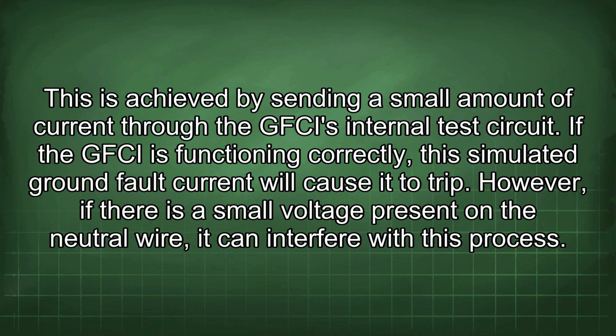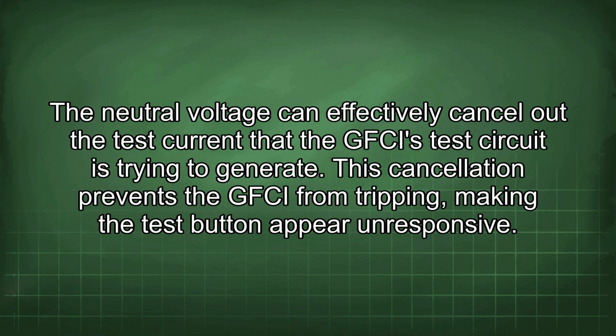However, if there is a small voltage present on the neutral wire, it can interfere with this process. The neutral voltage can effectively cancel out the test current that the GFCI's test circuit is trying to generate. This cancellation prevents the GFCI from tripping, making the test button appear unresponsive.